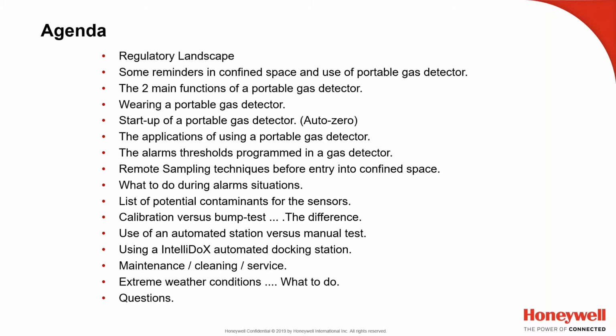I will reiterate that, very important. Applications, where they're being used and why for a portable gas monitor. The alarm thresholds program, the default alarm thresholds, and also where you can adjust them based on your own province, since in Canada it's more provincial - even in the States, they'd have different thresholds in California as opposed to others. Remote sampling techniques, proper way to do a confined space pretest, and what to do during alarm situations.